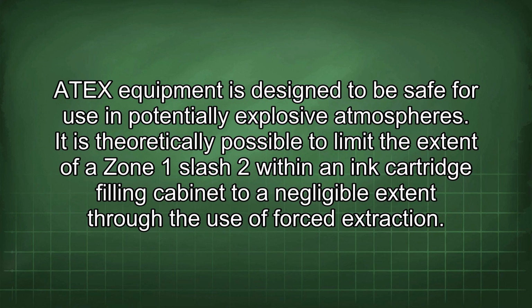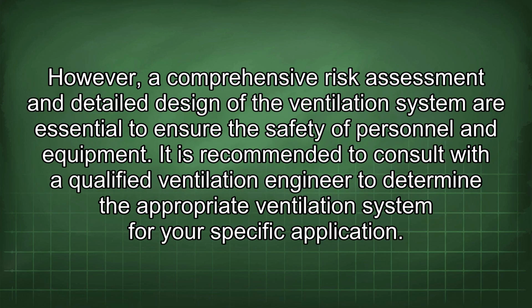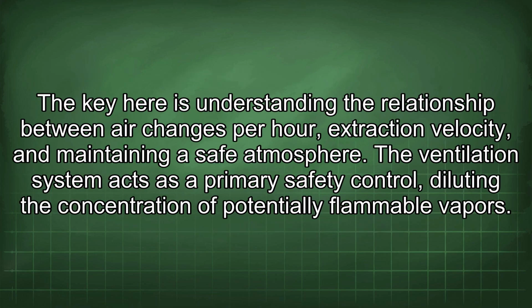It is theoretically possible to limit the extent of a Zone 1/2 within an ink cartridge filling cabinet to a negligible extent through the use of forced extraction. However, a comprehensive risk assessment and detailed design of the ventilation system are essential to ensure the safety of personnel and equipment. It is recommended to consult with a qualified ventilation engineer to determine the appropriate ventilation system for your specific application. The key here is understanding the relationship between air changes per hour, extraction velocity, and maintaining a safe atmosphere. The ventilation system acts as a primary safety control, diluting the concentration of potentially flammable vapors.